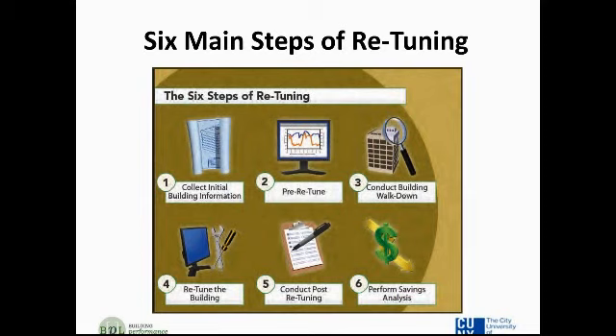So the main steps in retuning start with some initial building information. There's a pre-retune process, which gets into making sure that your building automation system is set up properly with the sensors, so you can understand what sensors are available, and also setting up your trend logs to look at a set of parameters prescribed by the building retuning measures. Then conducting your building walk down, looking for any physical issues that we can help you keep an eye out for. Then do the retuning itself, which is looking at the actual trend logs, diagnosing any issues you may have in your building, which we'll cover some of the areas, and then taking any corrective actions that you have identified.